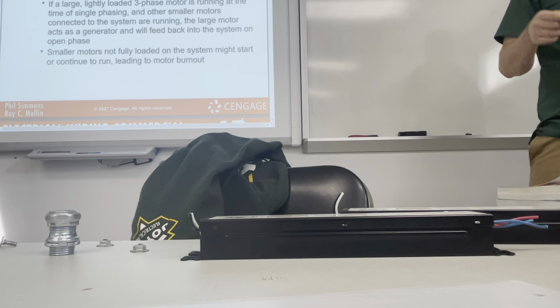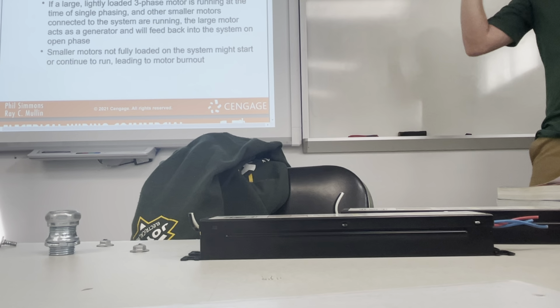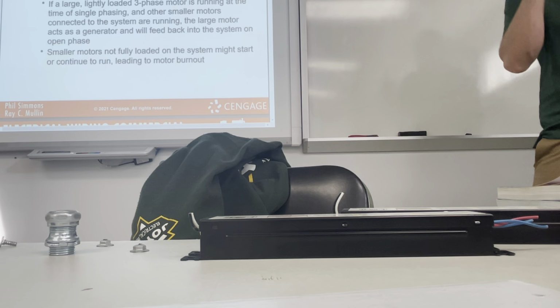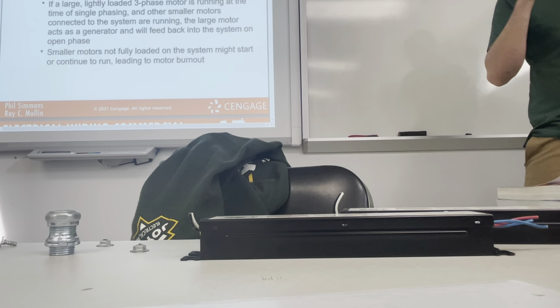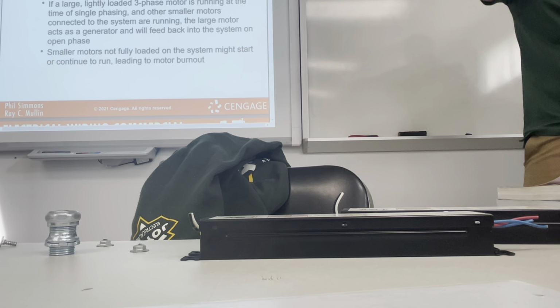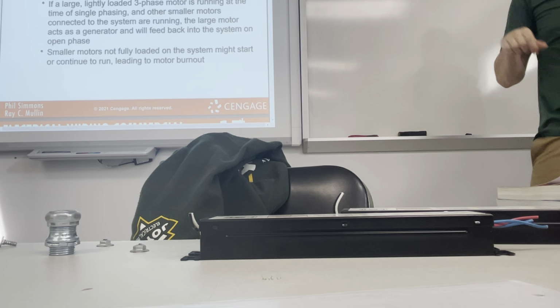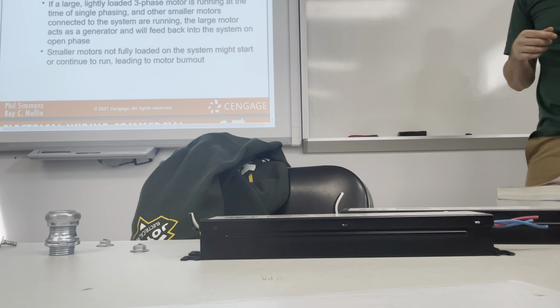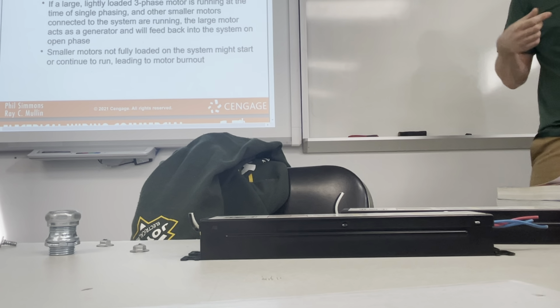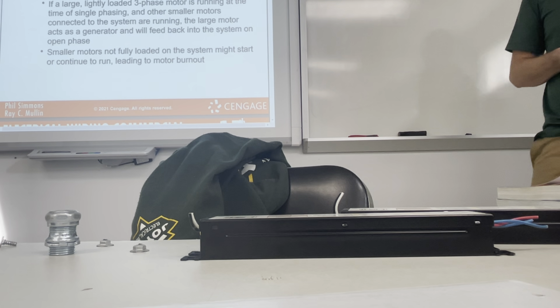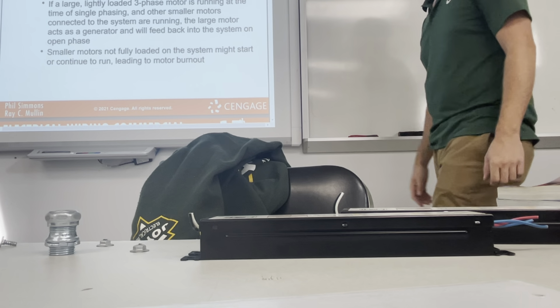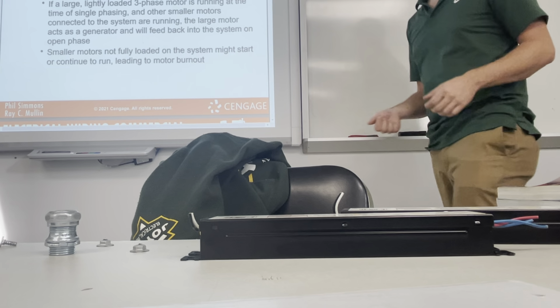People get fried just accidentally touching the lines. They think this motor is disconnected. I'm just pulling it off the system. It's just held on by sprockets. Oh yeah, I can take this motor off while the rest of this is running. It doesn't need this motor. It's got 30 other ones. You can still get annihilated by touching those lines. If that shaft is spinning, it's going to create electricity. So just please watch out for that. It doesn't happen super often, but you should be aware of it.